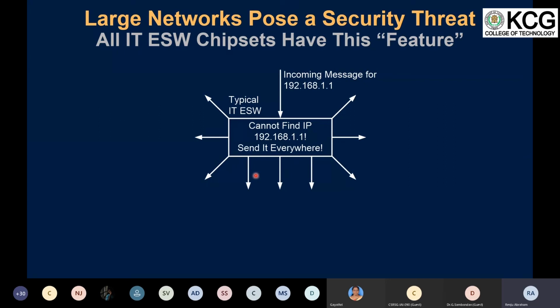Chipsets used in IT Ethernet switches create a message storm when faced with a high volume of incoming data. If an IT Ethernet switch detects a message from an unknown IP address, it sends the message to all ports. This means that during the time RSTP recovers, the IT switch itself will cause a storm of data, causing data loss on protection and control networks that use commercial grade IT layer 3 Ethernet switches, which in turn can create a power system blackout.